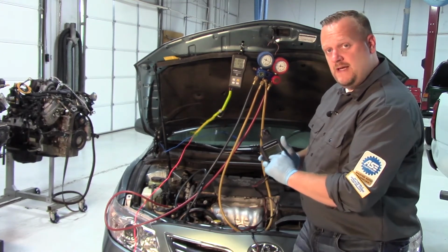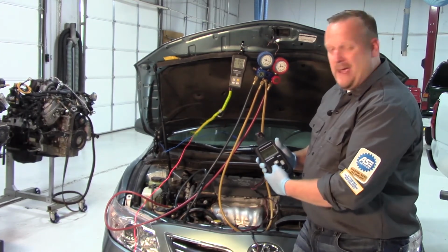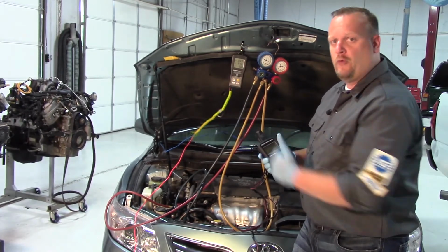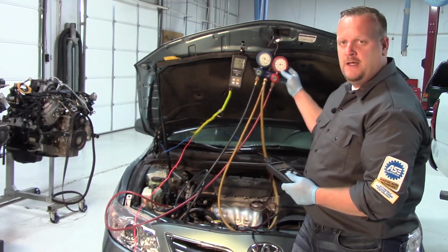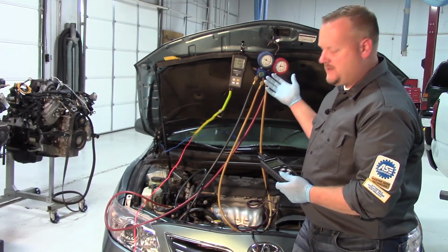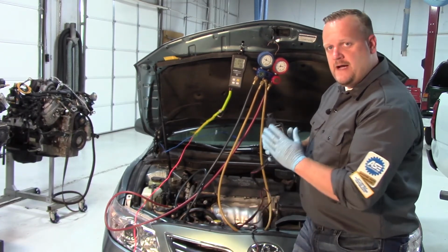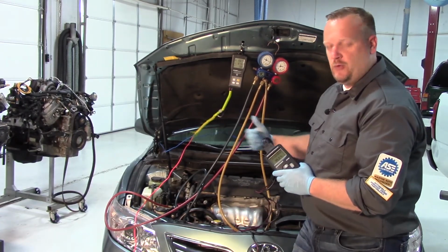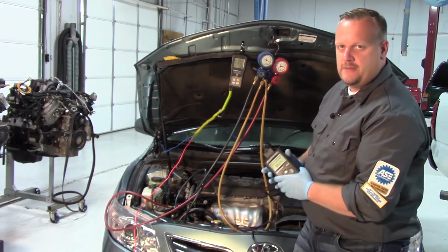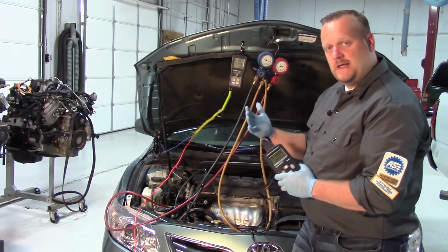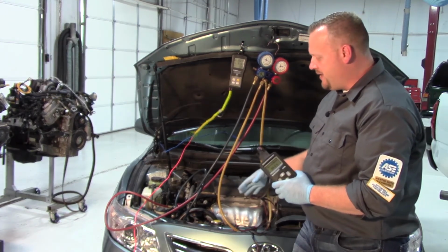If we weren't seeing this type of signal, I could go into manual mode and ramp the compressor up or down to see if there were any corresponding changes on my gauges. But we've already verified that the control module is making the request—the compressor is just not up to the task. So once again, it's time to replace this compressor.